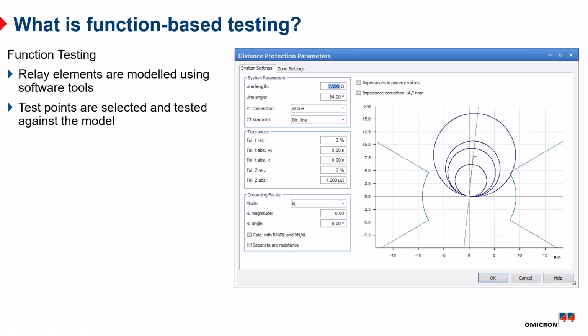Now, of course, back in the day when I first got started testing digital relays, there wasn't much in the way of this. So you had to create the model in your head and come up with the stimulus and the anticipated response, and do all that yourself, which was obviously much more time consuming. We had lots of Excel spreadsheets to automatically calculate a lot of these values for us. And as you can probably imagine, some of the test stimulus that we were using at the time was not terribly realistic. We would apply balanced three-phase voltage and one current, or do an impedance relay or something like that. Typical way of doing it. So we did it more to simplify the testing rather than verify that the relay was actually set in a way that it was going to actually work.